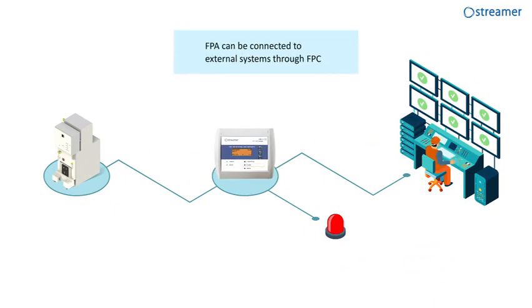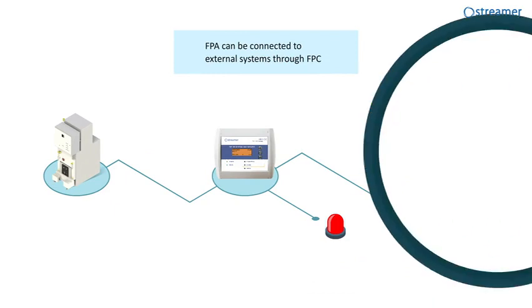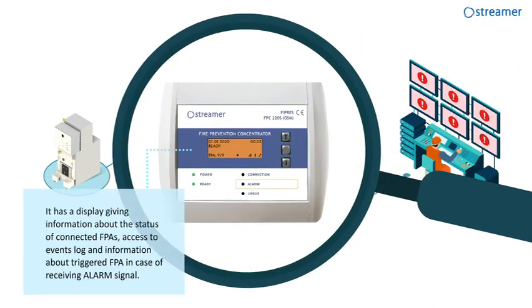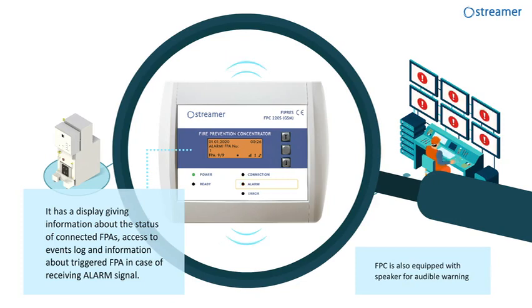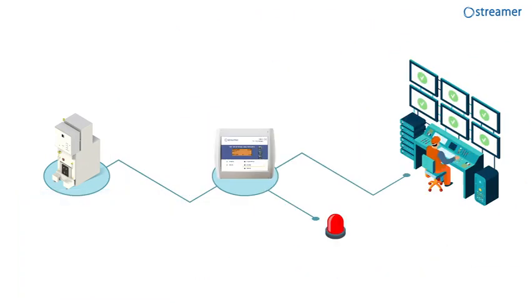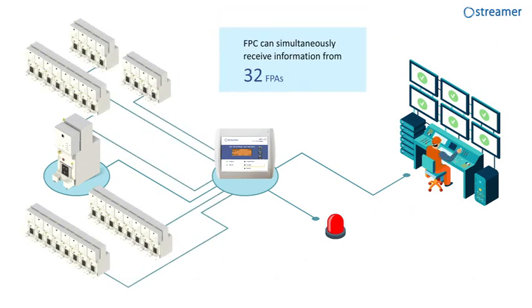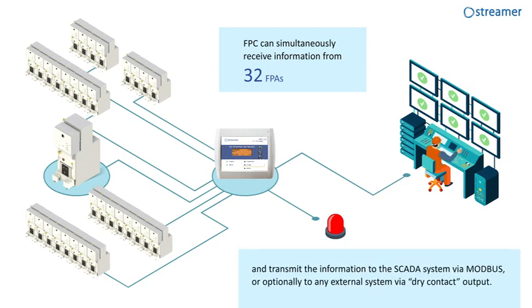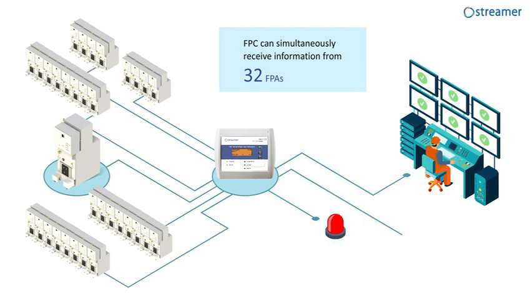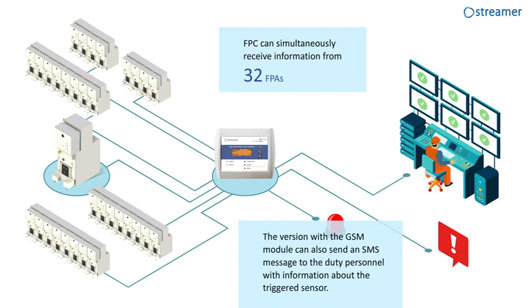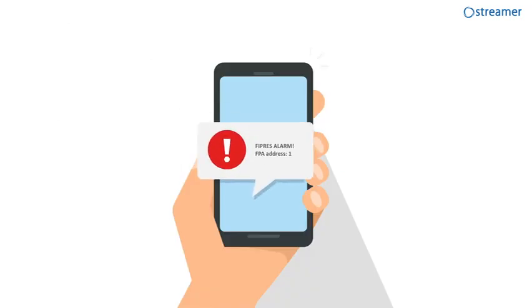FPA can be connected to an external system through FPC. It has a display giving information about the status of connected FPAs, access to events log, and information about triggered FPA in case of receiving alarm signal. FPC is also equipped with a speaker for audible warning. FPC can simultaneously receive information from 32 sensors and transmit the information to the SCADA system via Modbus or to any external system via dry contact output. The version with the GSM module can also send an SMS message to the duty personnel with information about the triggered sensor.